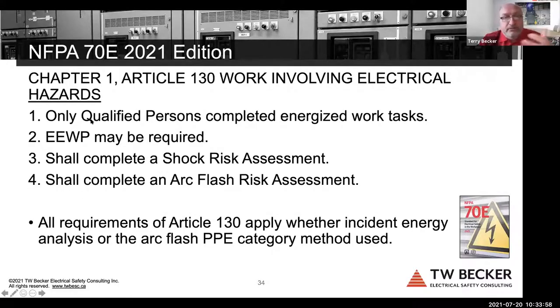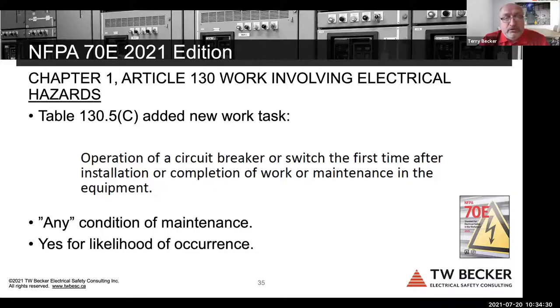And again, it basically implies that once we can't establish an electrically safe work condition, the requirements of 130 are performed by a qualified person, and you may need the permit, because the permit's still there. There really wasn't any big changes to the permit requirement. And then this qualified person has to complete a shock risk assessment and an arc flash risk assessment themselves, right? And that's where the risk assessment procedure, I think, has some confusion. The risk assessment procedure is performed by the employer's electrical safety committee, and then we have the worker doing their individual arc flash and shock risk assessments.